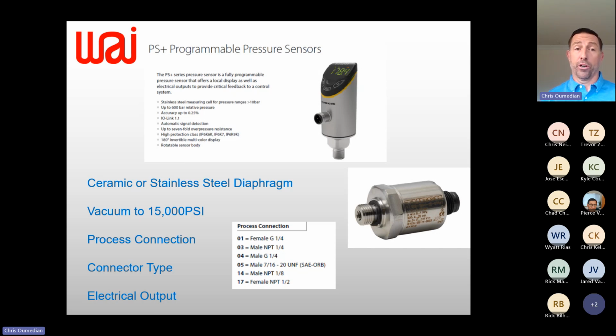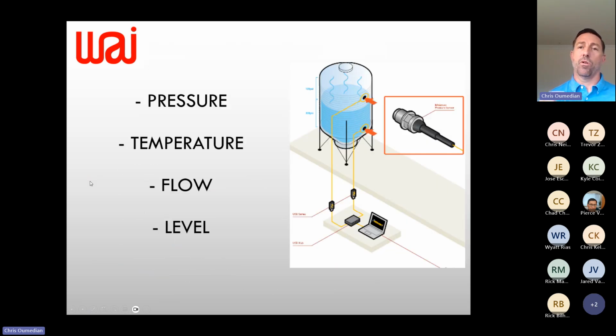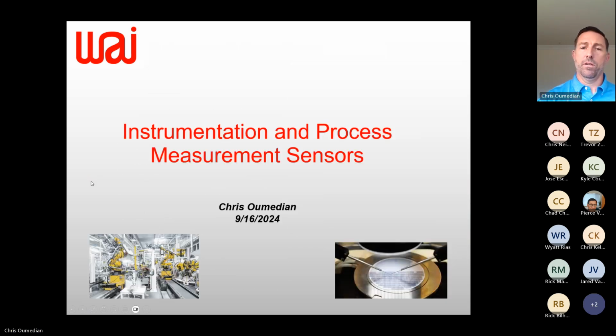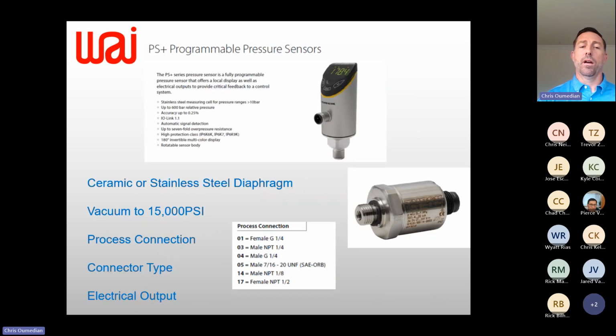you'll hear a burst pressure, and that is the pressure above what it's rated for that this device will take before you are at risk of cracking or damaging that cell, where your output now doesn't function correctly. So, ceramic is a more brittle and more solid diaphragm. Stainless steel gives you a little more flexibility, more for higher pressures, and typically has a higher burst multiplier.